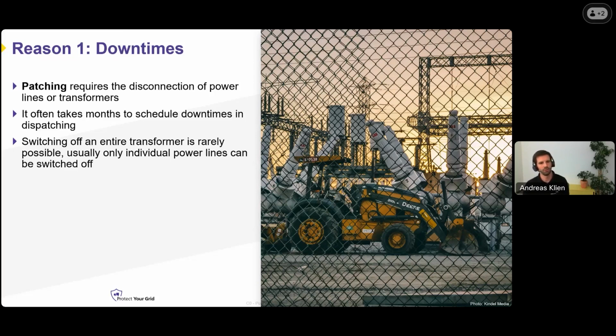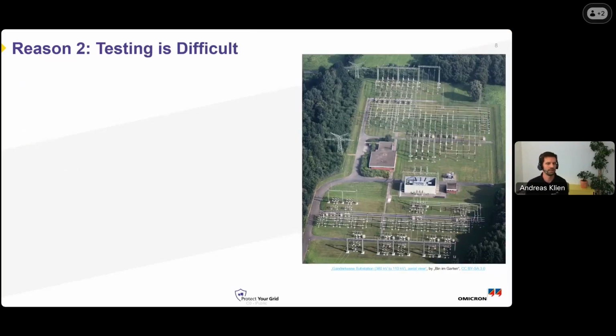The more important and more difficult reason is reason number two: testing. Testing is so difficult. This is an aerial picture of a substation, and you see all these connections and switching elements. There are so many switching combinations possible, and there is logic needed to make sure you're not producing a short circuit with the switching you're doing. It is complex logic that needs to be programmed specifically for a particular substation and its surrounding circuit.